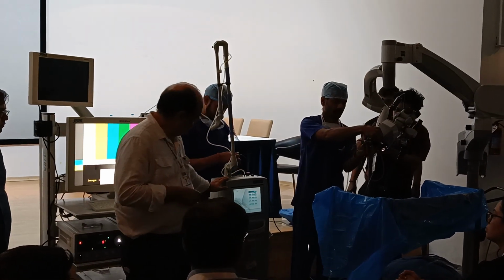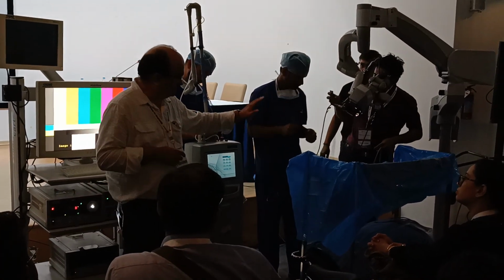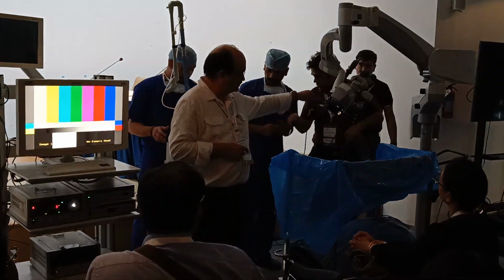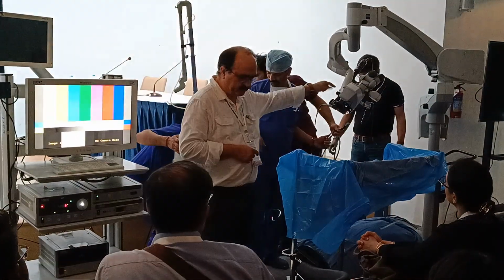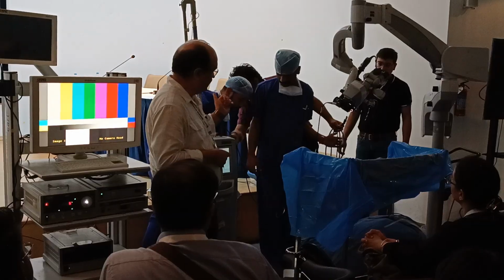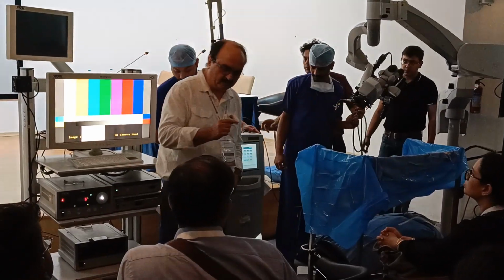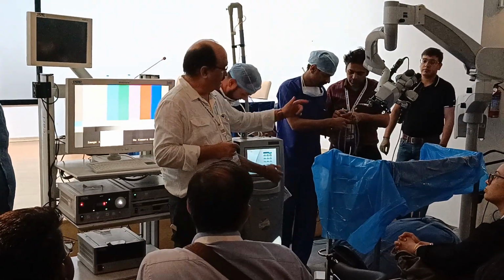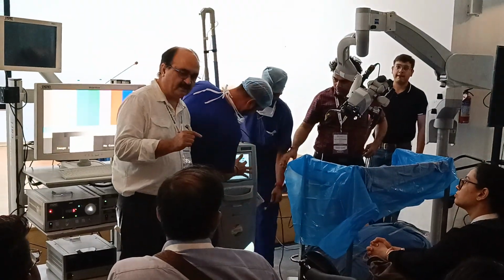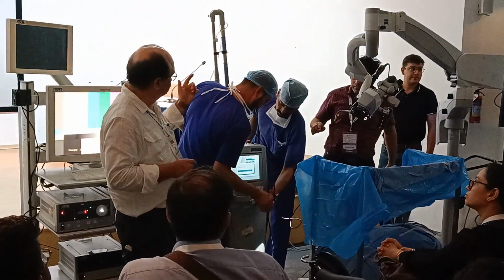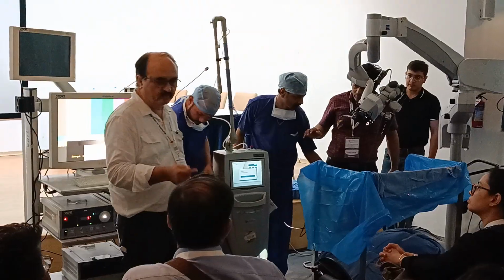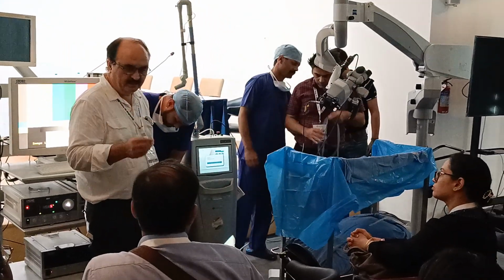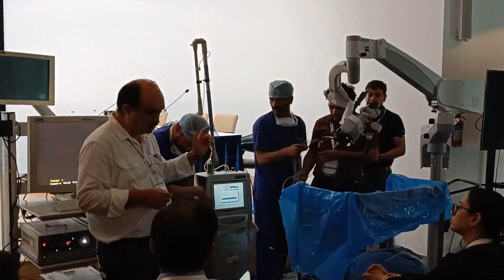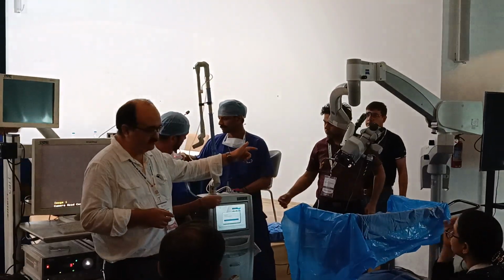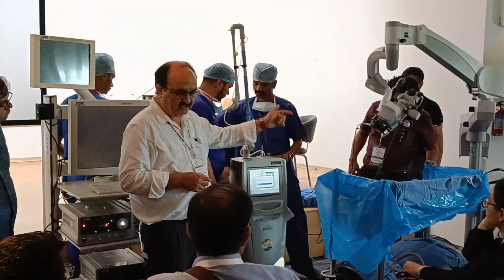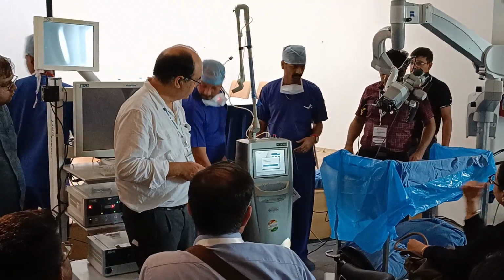Now, basically, when we talk about larynx, this black part is called the microscope. You couple the microscope with the laser, and like we were showing, you can make different beams. Unless you have a micromanipulator, you can't have a scanner. You can do lasers like this with a handheld probe if you want to work in the oral cavity. But if you want to work in the larynx, you have to have a delivery through the microscope, with attachment to the micromanipulator.